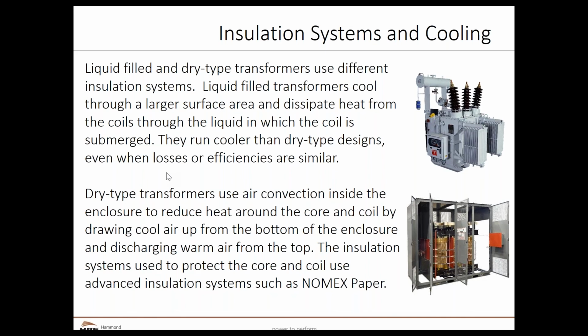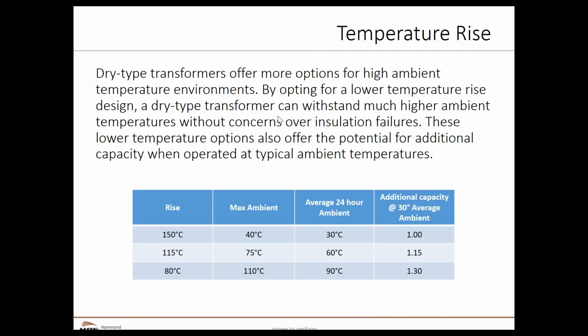Otherwise, we will be building a much, much lower temperature rise transformer with a dry type than is probably needed, and the cost and size will escalate accordingly. So again, we've had some other graphs here in the temperature rise options. You can see here that depending on the temperature rise, an 80°C temperature rise transformer, which is a common option in dry type, can actually handle an ambient temperature hotter than the boiling point of water. You don't have those options with a liquid filled transformer.